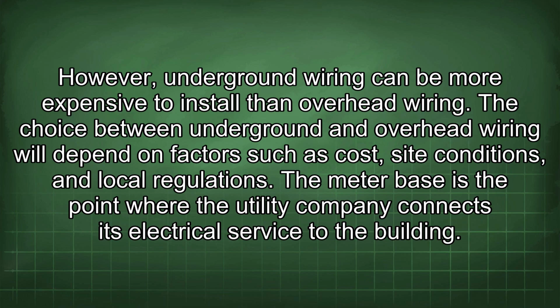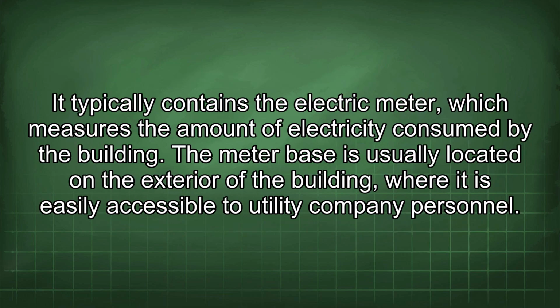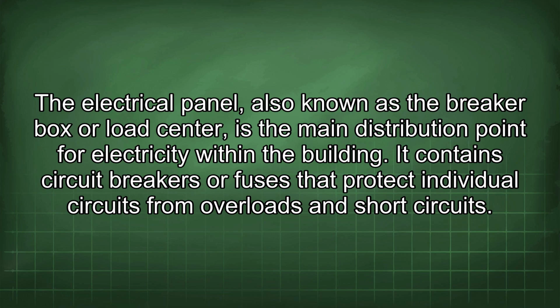The meter base is the point where the utility company connects its electrical service to the building. It typically contains the electric meter, which measures the amount of electricity consumed by the building. The meter base is usually located on the exterior of the building, where it is easily accessible to utility company personnel. The electrical panel, also known as the breaker box or load center, is the main distribution point for electricity within the building.